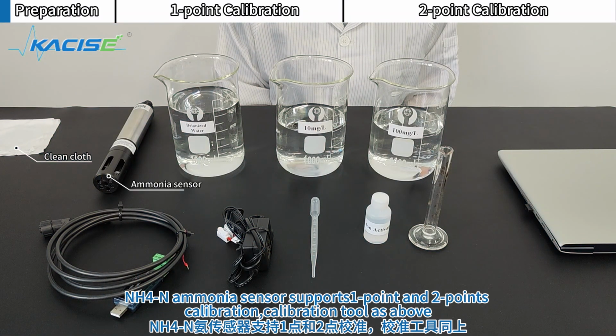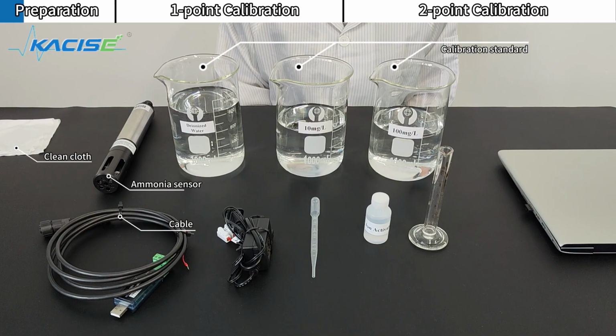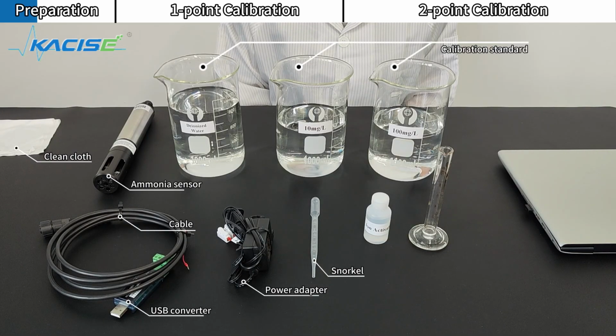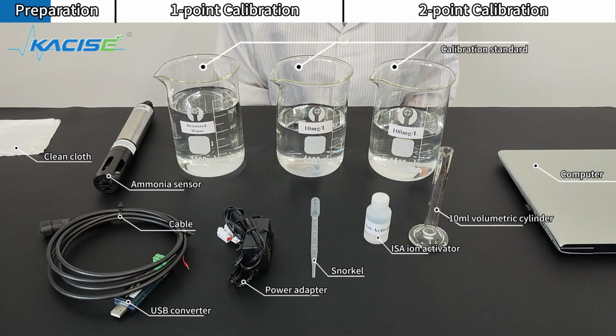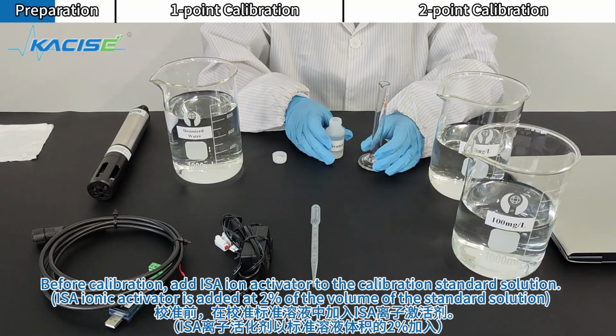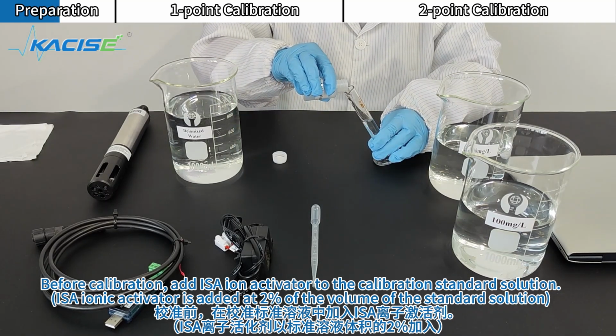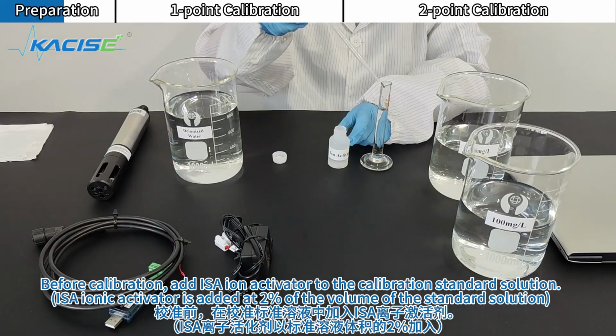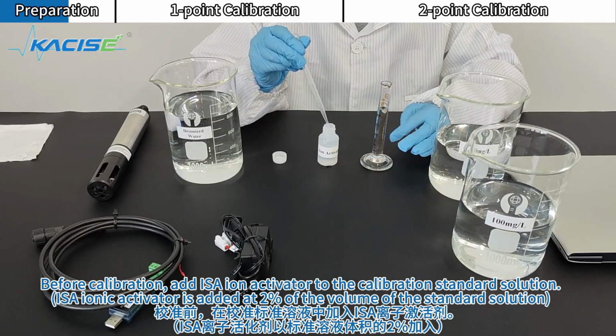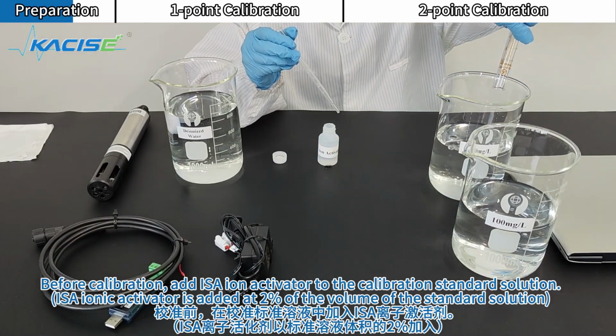NH₄-N Ammonia sensor supports 1 point and 2 points calibration. Calibration tool, as above. Before calibration, add ISA ion activator to the calibration standard solution. ISA ionic activator is added at 2% of the volume of the standard solution.